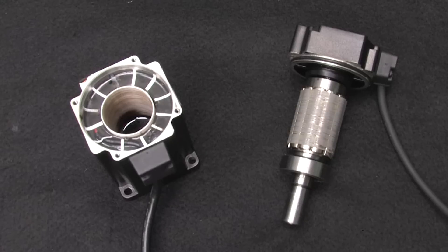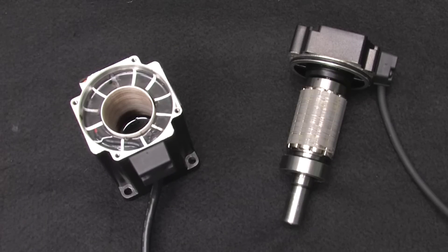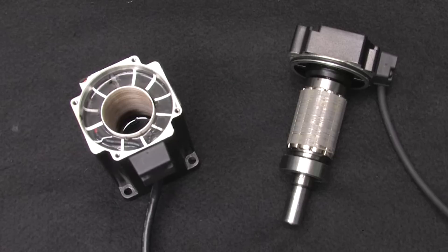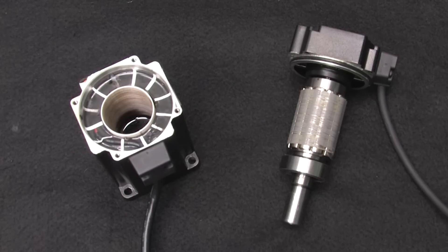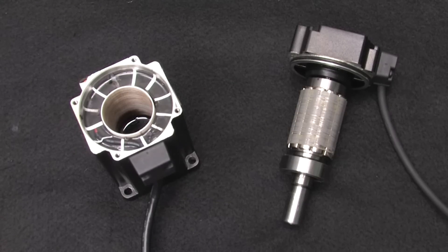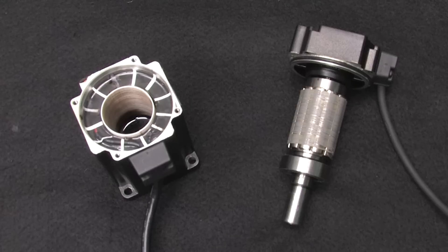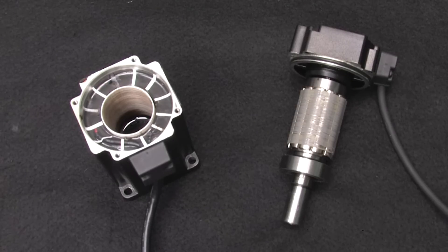And if you're thinking this is going to confuse the drive, yeah, the drive is not going to understand what's going on. It expects to apply a certain amount of current into the stator and get a specific response from the encoder reacting to that. When it doesn't see it, it's not going to be a happy camper. So we're going to have to fake it out.